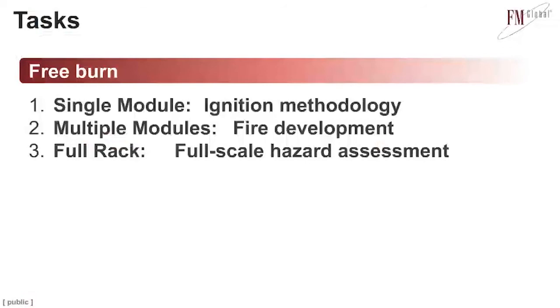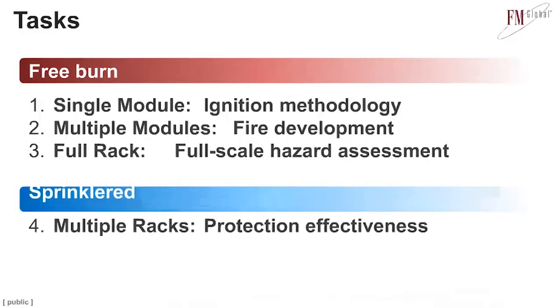This is just summarizing some of the points that Tom put together. The single module test was really to look at the ignition methodology, making sure that we have a consistent way of causing a fire, thermal runaway followed by fire, in these modules, and then looking at multiple modules to see development up to full-scale rack testing, to really get a full assessment of the hazard of at least a couple of commercial-scale systems. And then following that up with the sprinkler tests, again, to show the effectiveness of protection.